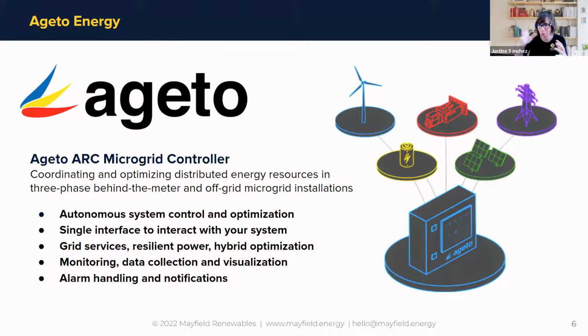So to me, it was like the controller brought it all together and actually had the ability to throttle back the PV inverters when the batteries were full. It can talk to the BMU - it communicates with the Blue Planet energy system and sends its signals. It did have the capability of working with the generator. We ended up with a different route when we coordinated with the generator on that project, but with other projects, it could also talk directly to the generator. And then of course, it's telling the microgrid interconnect device when to open and when to close.